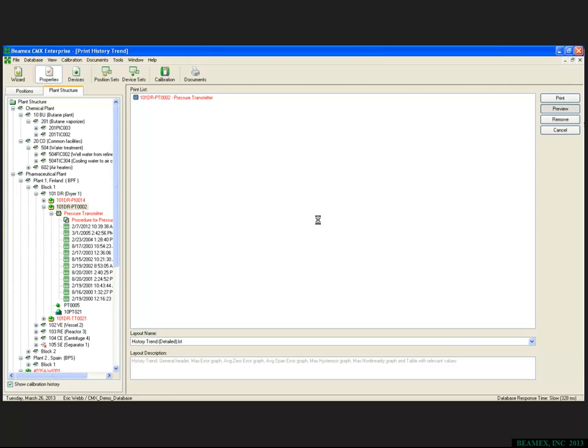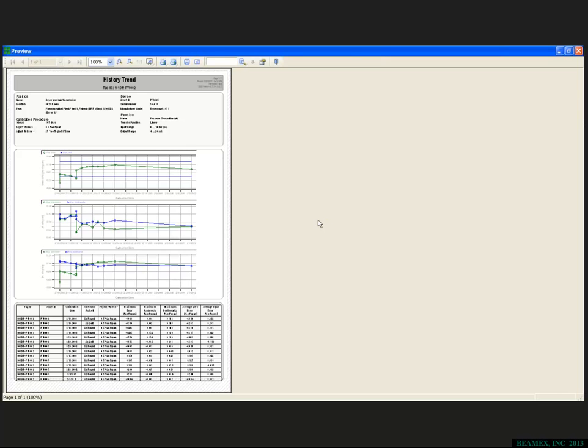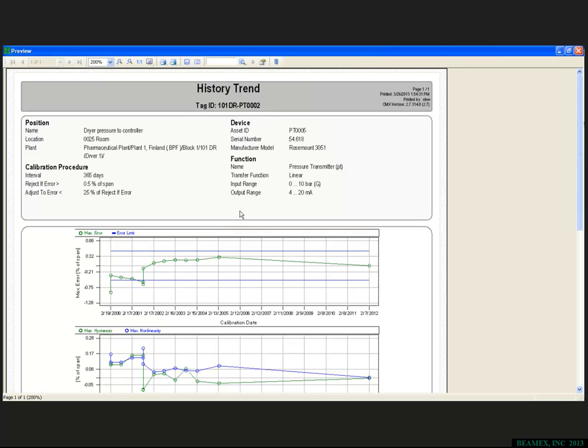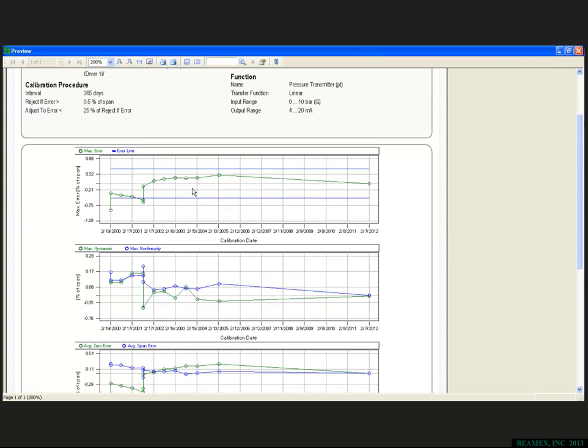And hopefully I answered the question with regards to the rule of thumb well enough, and if I didn't, then I'll be more than happy to take that a little further here in just a moment. But what you're seeing here is a history trend of that particular tag number. It gives you position, name, all of the information that we saw earlier. The calibration interval is now 365 days. The reject error is the same, it's 0.5% of span. The device ID function, this is a pressure transmitter to a linear device. It gives you the input and output range of how it's calibrated.